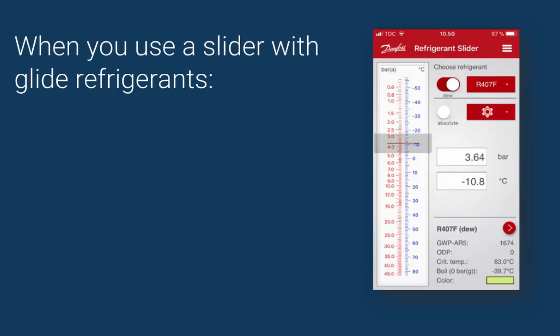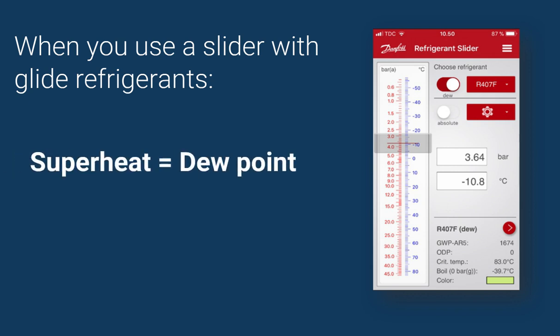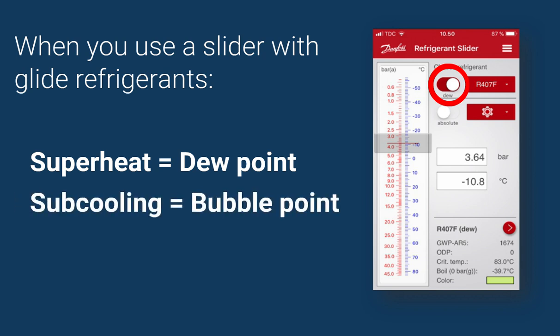When you're using a PT chart with glide refrigerants, you also need to know that when you're looking for superheat, you should look for the dew point or dew line values. And when you look for subcooling, you should look for bubble point or bubble line. As a silly rule to remember: look for dew-per heat and bubble cooling.